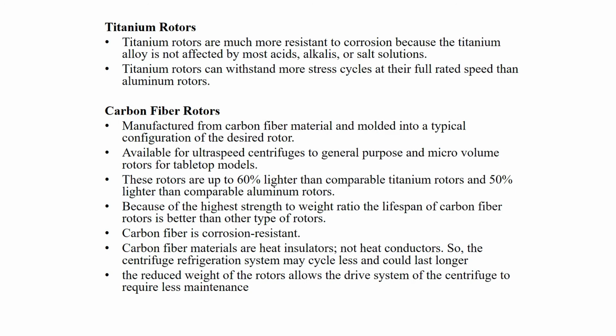And carbon fiber is an excellent heat insulator. So therefore it can withstand heat that is generated by the rotation of the rotor. So your investment in terms of a refrigeration system in a centrifuge can be minimized. So therefore there are several advantages for a carbon fiber rotor.